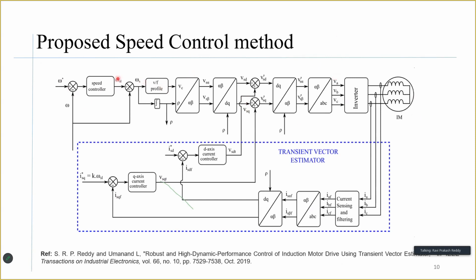However, and similarly, since the steady state portion is based on the V by F control, there is no need for the estimation for slip, right? For example, if you look at the steady state portion, slip is something that I can readily take from my V by F control portion. So therefore, I do not have to worry about its dependency on the rotor parameters like the rotor inductance and the rotor resistance, which is what would happen in typical vector control or indirect field oriented control schemes.